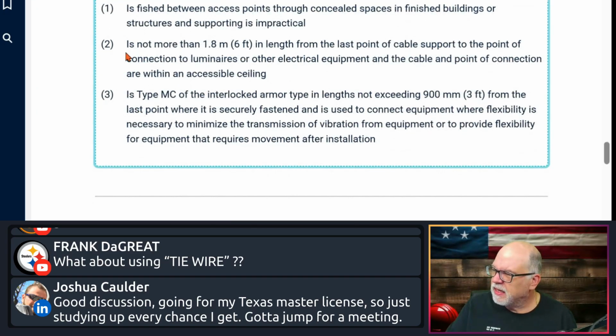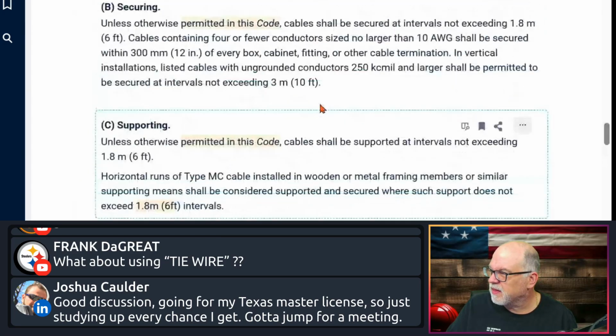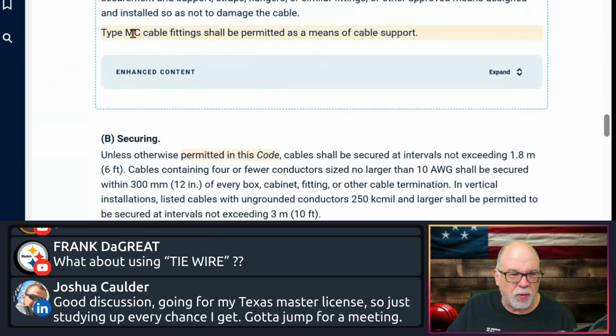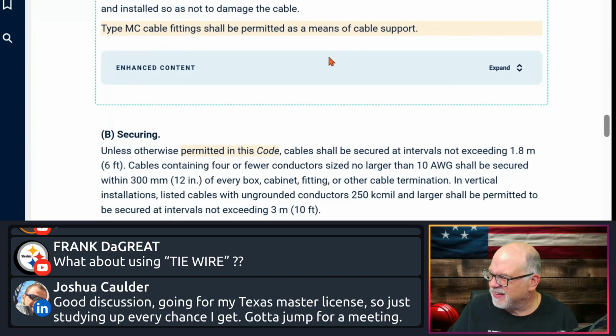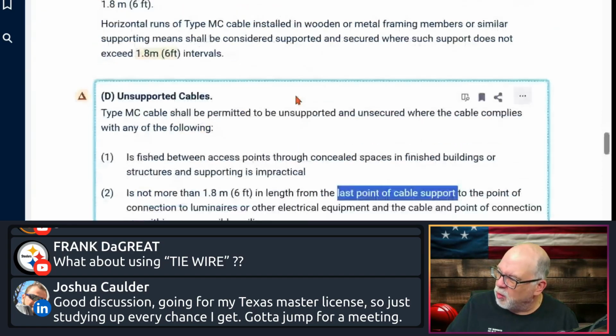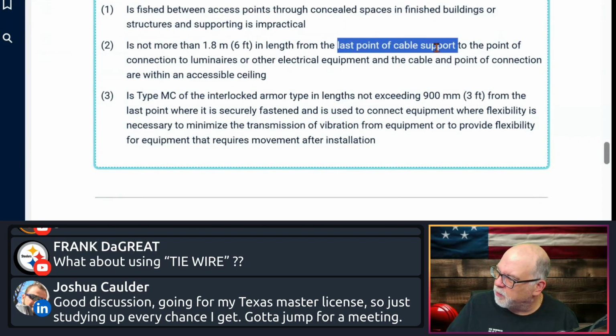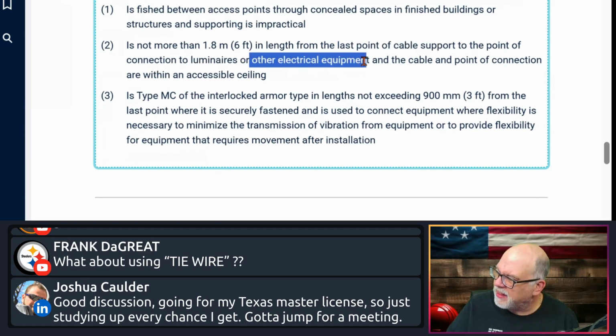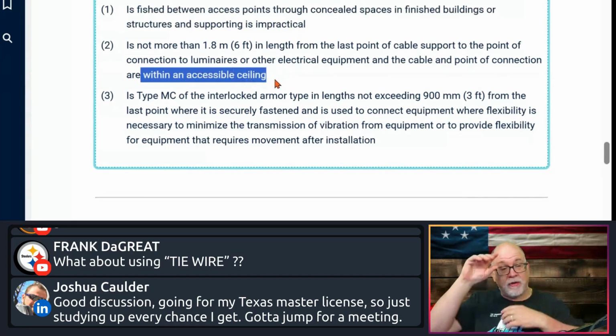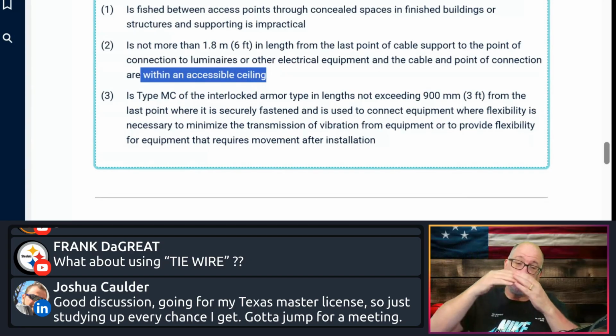Next, it says, it is not more than 6 feet in length from the last point of cable support. Okay. And that's what's important about this rule right here. The fitting is considered a support. You see where it's going with this? So it says, if it's not more than 6 feet from the last point of cable support to the point of connection to a luminaire or other electrical equipment, and the cable and point of connection are within an accessible ceiling. So that's going from a box down to a piece of equipment. I can go up to 6 feet.